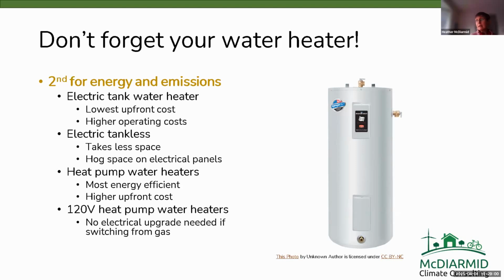Really exciting to me are these new 120 volt heat pump water heaters. My next water heater will likely be one of these. The exciting part is that it runs on 120 volts, off a regular outlet. When switching from a gas water heater to an electric one, you often don't have a 240 volt outlet or electrical line there to connect a conventional tank or heat pump water heater to. These 120 volt heat pump water heaters are designed for those homes so you don't need any electrical upgrade when switching from gas.